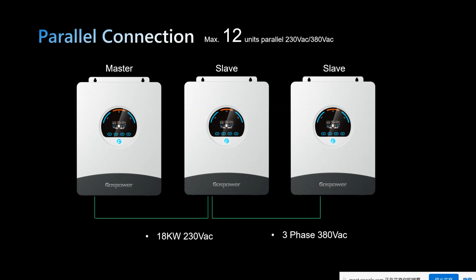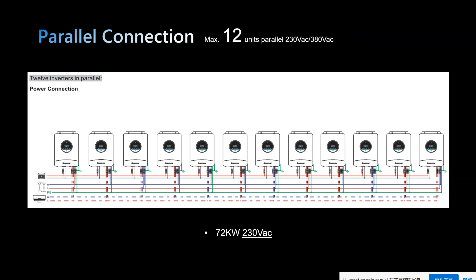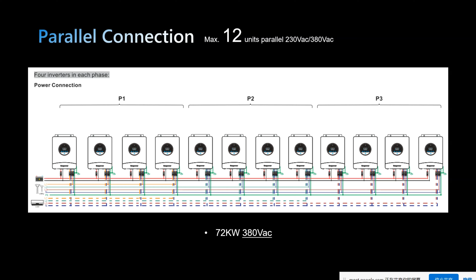As I just mentioned, the maximum number of inverters that can be connected in parallel is 12 units, so the maximum size of the system is 72 kilowatt. This photo shows 12 inverters in single-phase connection, and another photo shows 12 inverters in parallel with 3-phase AC output, with 4 inverters per phase. You can also find more parallel connection ways in our user manuals.